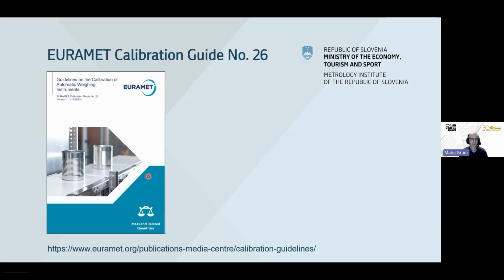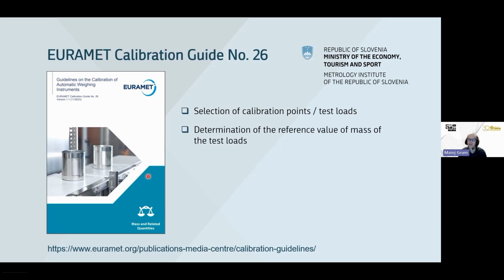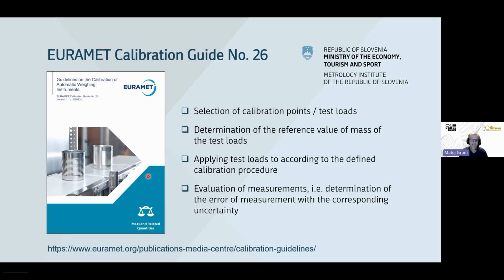Basically, the structure of the guide followed the procedure of the calibration. First of all, it's dedicated to the selection of calibration points, selection of test loads. The next step is determination of the reference value of mass of these test loads. As the next step, it's necessary to apply the test loads according to procedures defined in the guide. Different measurements are carried out, and based on these measurements, it is possible and necessary to evaluate the measurements, to determine the error of measurement, and to evaluate the corresponding uncertainty of measurement. And the results are reported in the calibration certificate at the end. So the guide also provides some instruction on which information is necessary to be included in the calibration certificate.